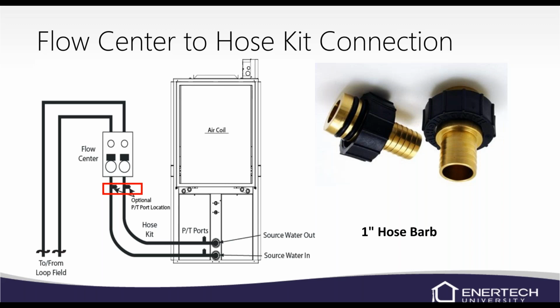Sometimes it's a little bit more difficult if you put them at the unit, because on a packaged unit, the water connections are underneath the return. So if you're a bigger guy, tall, I'm not, or just older and you don't like getting underneath the return, then it may be easier to put it at the flow center. If you put it underneath the return, you kind of got to get on your hands and knees down in there, and it's a little dark area. I'm a small guy, but I'm getting old, so I don't like to kneel down on that concrete floor. But sometimes you got to do what you got to do. I would recommend putting them at the flow center just for ease of checking things. But again, it doesn't really matter.